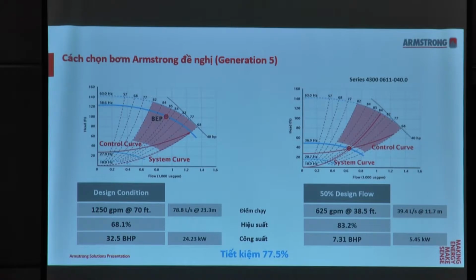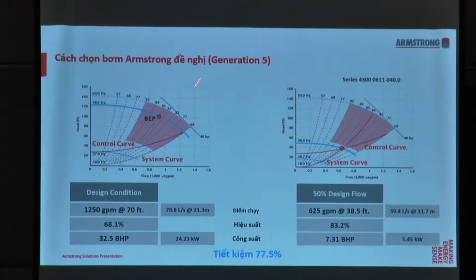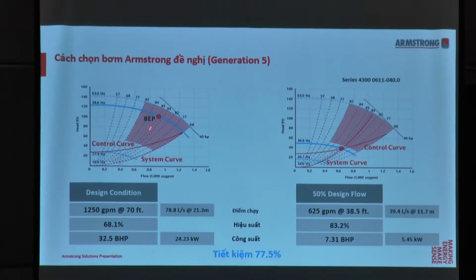Now, what does Armstrong do differently? Again, if you see, the best efficiency over here is at 85%. What we do is we select a point, or rather our duty point is to the right-hand side of the BEP. Okay, so even though at 100% our efficiency is 68.1%, we are considering part load. So let's take a look at part load. Our efficiency increases to 83.2%. And based on this calculation, again, we are able to achieve an energy savings of 77.5%. Again, this is above the ASHRAE 90.1 requirements of 70% energy savings at 50% design flow. Okay?